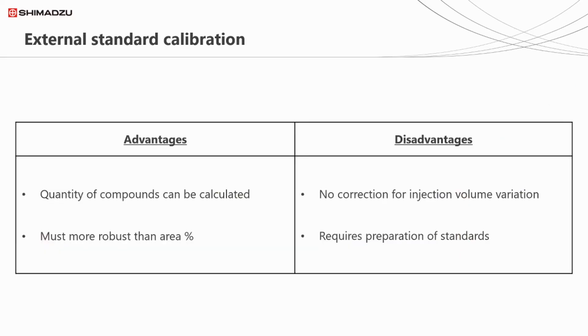This method is much more robust than area percent and is widely accepted as a reliable method for quantitation — we can determine exact quantities of compounds within the sample. But the method isn't completely without flaw: this version doesn't account for instrument variation, such as small discrepancies in injection volume. It's also more labour intensive, as it requires the preparation of calibration standards. You'd usually need a minimum of three concentrations to be confident your line of best fit is accurate, and ideally around five.